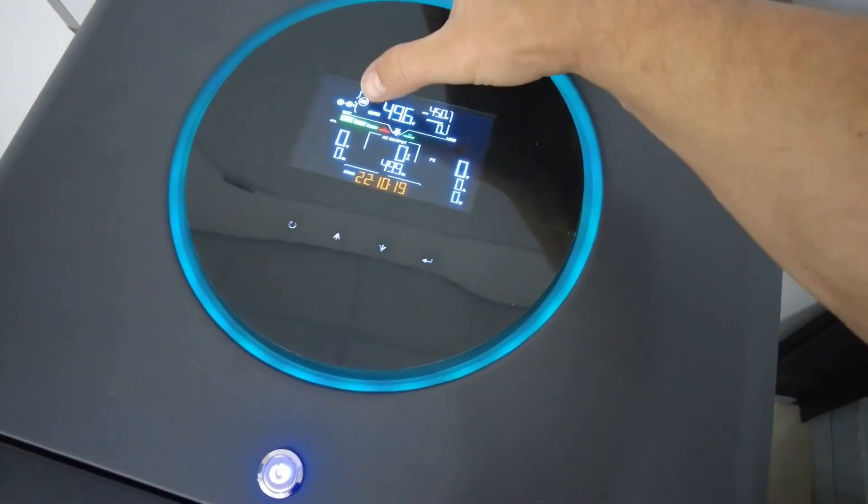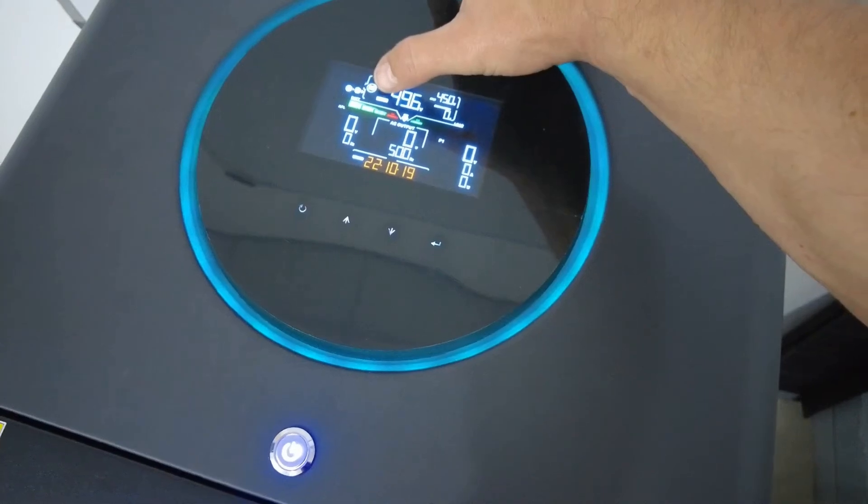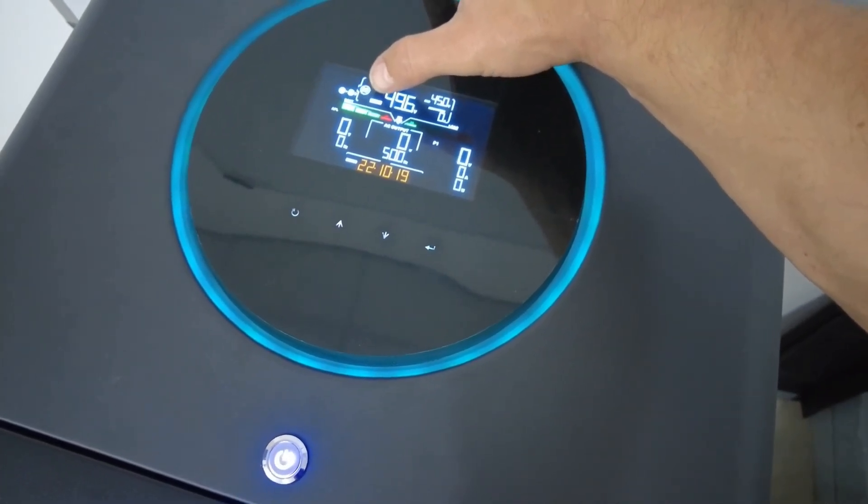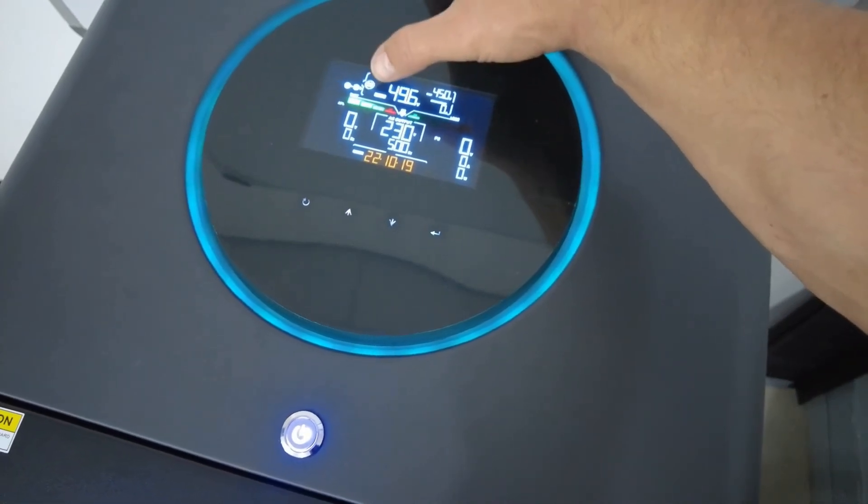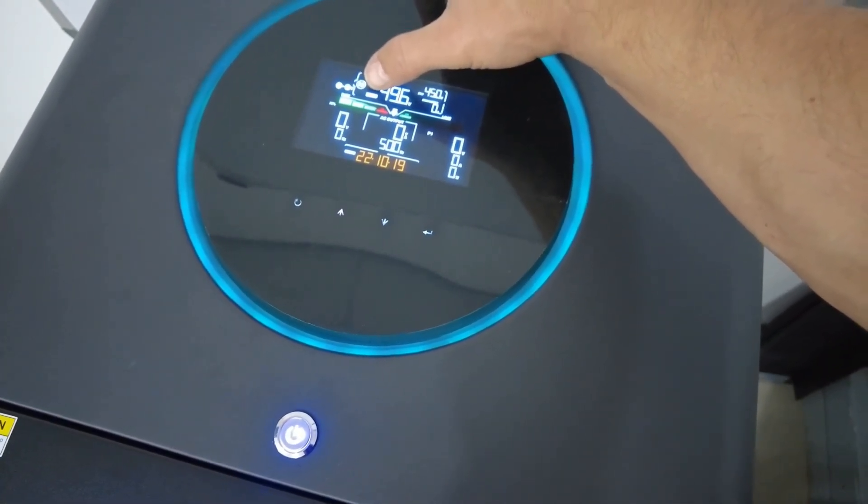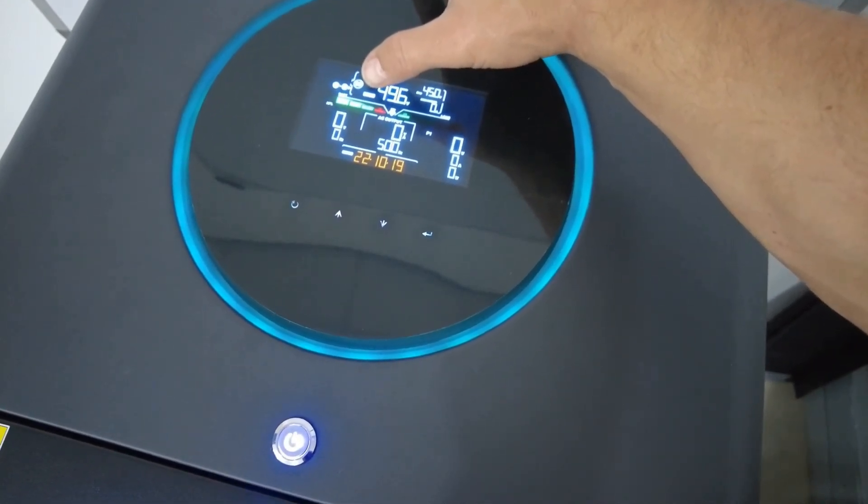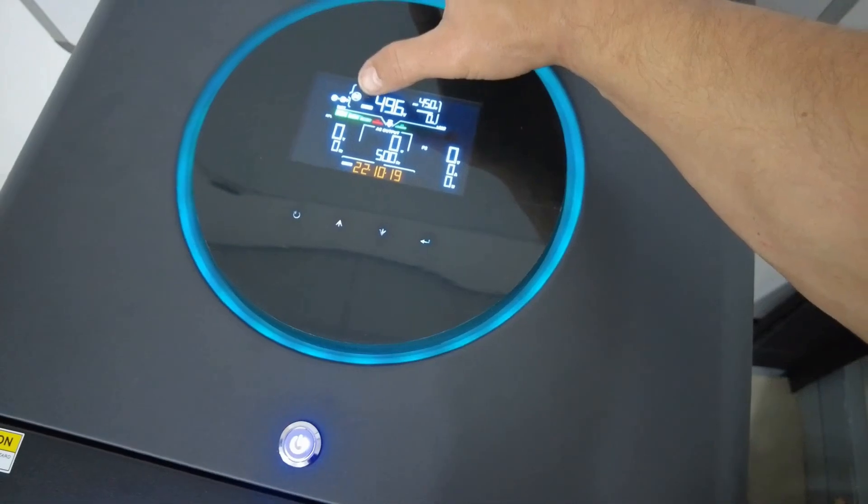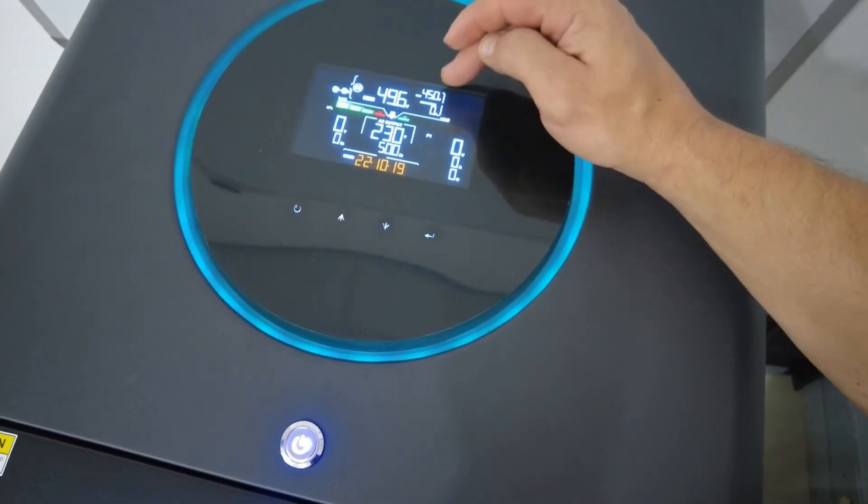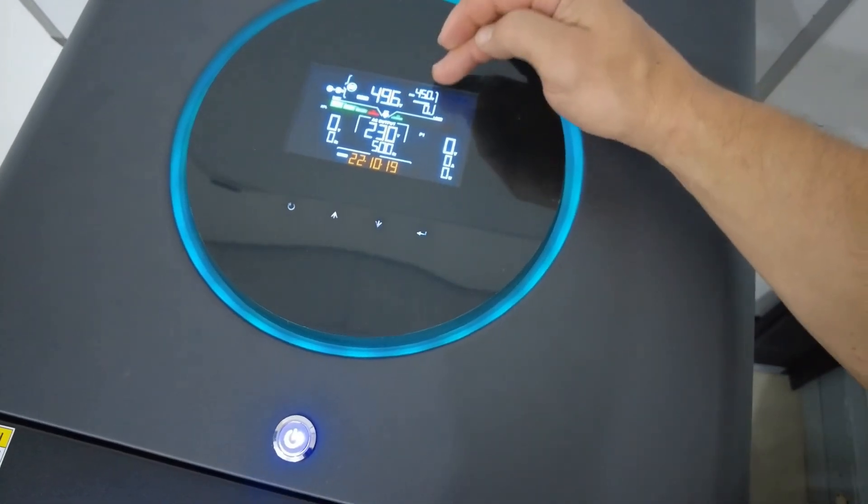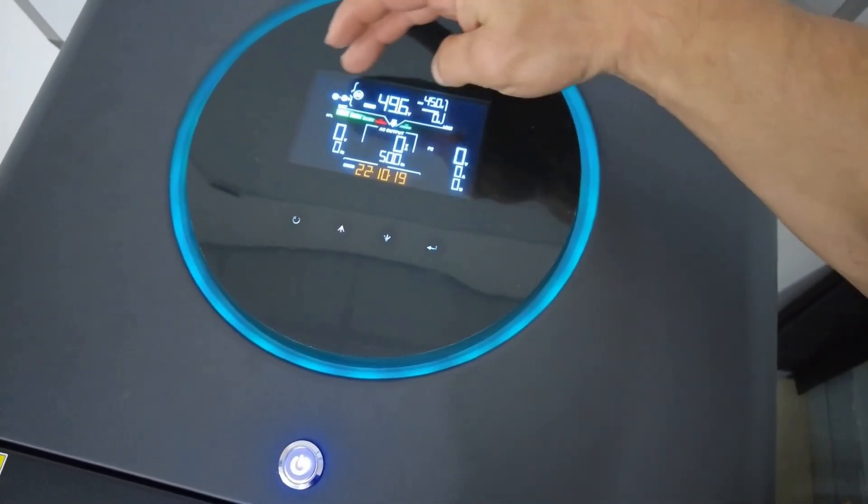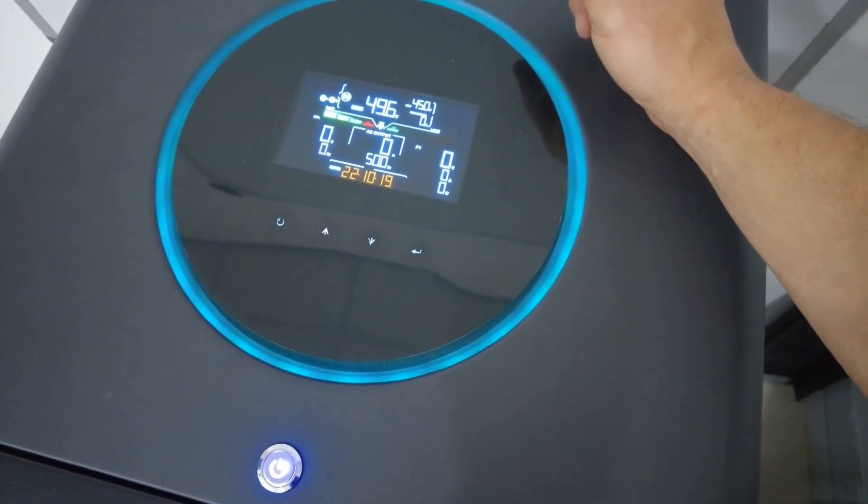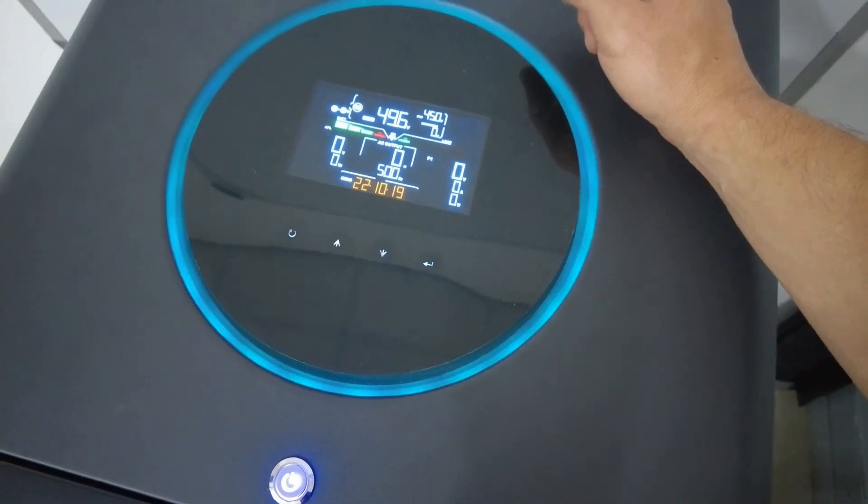Do take note, your lithium-ion icon is on, but do not take that as it's communicating. That's purely telling you the battery type. In this case, you set it to lithium-ion battery type. It's just informative. To be sure your BMS communication is up and running, have a look at your brackets and the flashing battery light. This flashing brackets is your telltale sign that the communication is up and running.